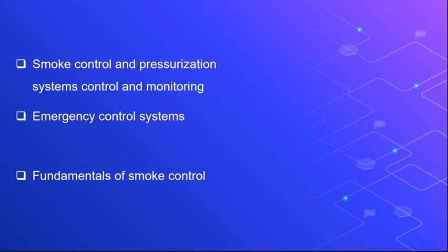Emergency control operations are carried out by control units within the hardware and software integrity of the fire alarm system. All kinds of control and command operations that can be done by the control system and security systems related to the devices by other systems such as building automation systems must in no way prevent the emergency control operations to be made from the fire control panel in case of fire or a similar emergency.